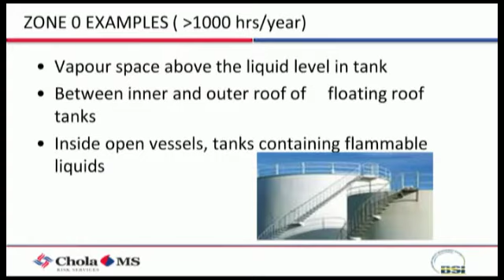Then in a year, putting all this together, if I need to classify an area as zone 0 or zone 1, it should fall greater than 1000 hours. If it comes only to 500 or 100 hours in a year, I might move this to zone 1. So those are the ways we classify that.